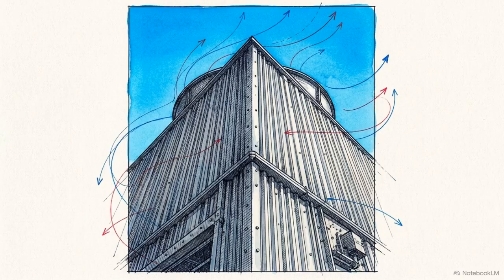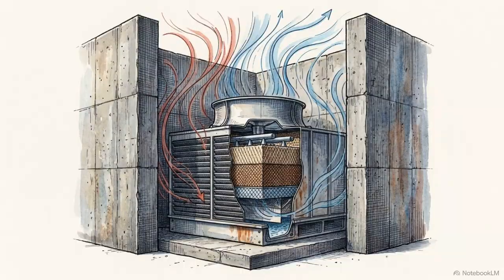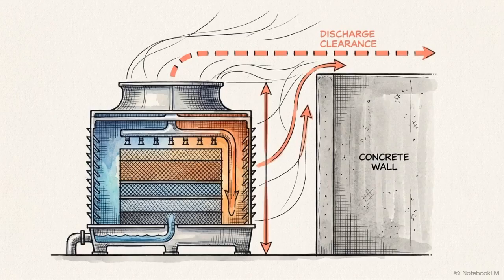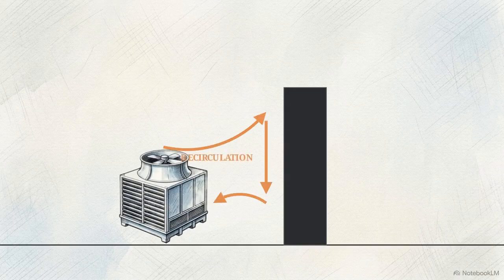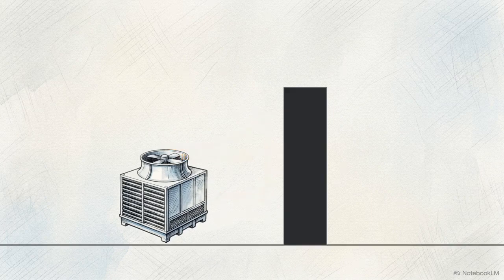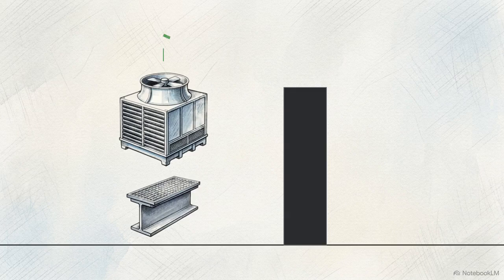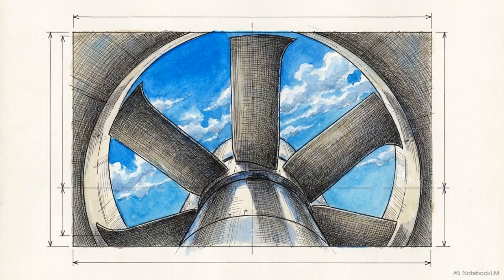Step 2 moves us from the sides of the unit to the top, where we have to manage the height of the architectural enclosures surrounding the equipment. The cardinal rule here is that the cooling tower's discharge point must sit physically higher than the top of any adjacent wall. Look at this cross-section. Warm exhaust hits the high wall and gets sucked back down into the intake vents. To fix this, either install discharge ducts or elevate the entire tower on a platform so the exhaust can safely disperse into the atmosphere. Clearing that discharge path ensures the tower will never choke on its own recycled hot air.